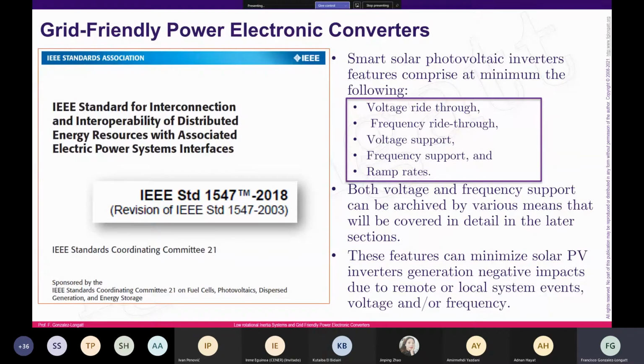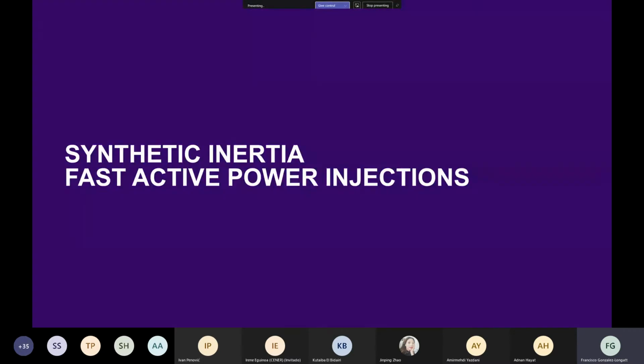after the IEEE standard 1547 established the new version of the requirements for interconnecting distributed energy resources, okay? This standard, 1547-2018, established that the converters used for solar power plants must include some new features: voltage ride-through, frequency ride-through, voltage support, frequency support, ramp rates, and also the possibility of including communication using different protocols, including IEC 61850, okay? I would like to close this presentation with some demonstration about synthetic inertia and some converters, okay?